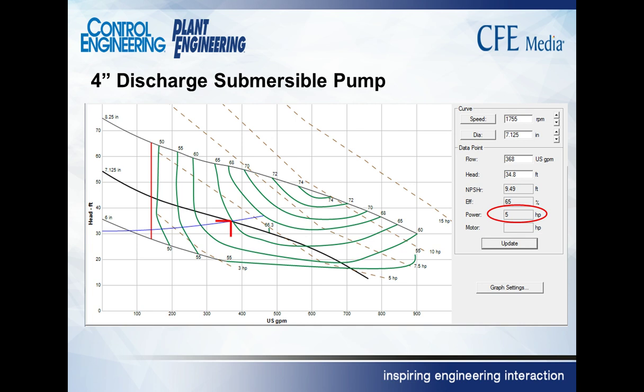And I'll just do it with slides. Okay, so I was going to show you live, but I'll show you here just on the slides. Here's that pump curve and system curve for that sewage lift station. And we're looking for 368 gallons per minute, 34 feet of head. One thing we could do with this pump, it has had the impeller trimmed from a little over 6, I can't read that. The impeller's been trimmed down quite a bit.